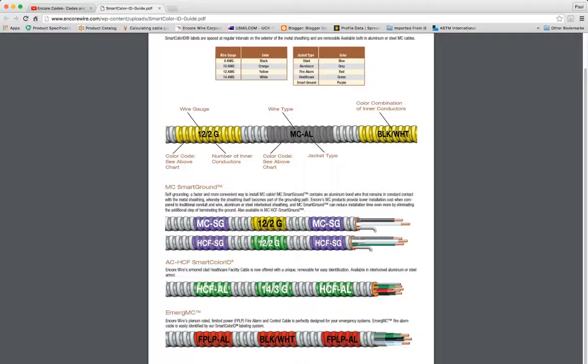Next, we have AC Healthcare Facility, same application here. You see that HCF, AL stands for the aluminum armor. It tells you there's a 14-3 with ground in there, and again, it is healthcare facility. The healthcare AC cable, the armor in itself is considered an equipment grounding conductor under 250.118. But in order to make it a healthcare facility, as always, in accordance with 517.13 B, we have to add an insulated equipment grounding conductor. And that's what we've done here. That's what turns a normal AC into a healthcare facility AC.